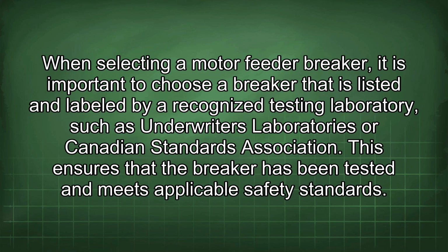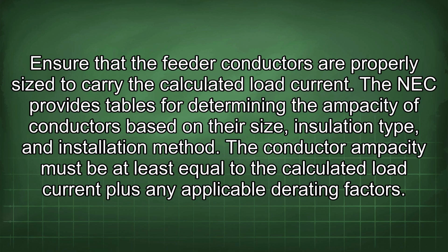When selecting a motor feeder breaker, it is important to choose a breaker that is listed and labeled by a recognized testing laboratory, such as Underwriters Laboratories or Canadian Standards Association. This ensures that the breaker has been tested and meets applicable safety standards. Ensure that the feeder conductors are properly sized to carry the calculated load current. The NEC provides tables for determining the ampacity of conductors based on their size, insulation type, and installation method. The conductor ampacity must be at least equal to the calculated load current plus any applicable derating factors.